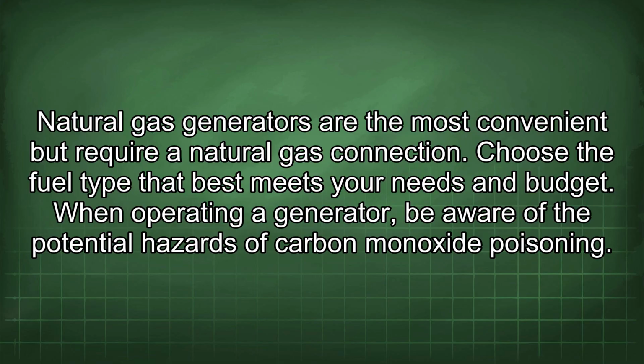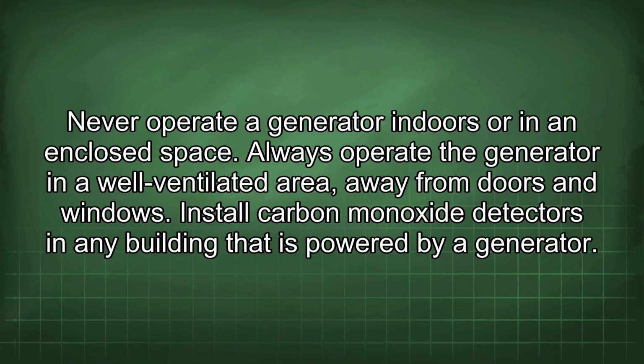When operating a generator, be aware of the potential hazards of carbon monoxide poisoning. Never operate a generator indoors or in an enclosed space. Always operate the generator in a well-ventilated area, away from doors and windows. Install carbon monoxide detectors in any building that is powered by a generator.